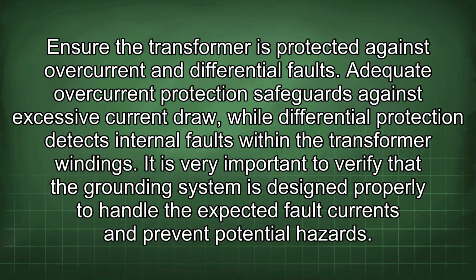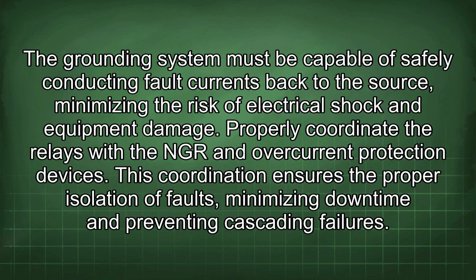Ensure the transformer is protected against overcurrent and differential faults. Adequate overcurrent protection safeguards against excessive current draw, while differential protection detects internal faults within the transformer windings. It is very important to verify that the grounding system is designed properly to handle the expected fault currents and prevent potential hazards. The grounding system must be capable of safely conducting fault currents back to the source, minimizing the risk of electrical shock and equipment damage.